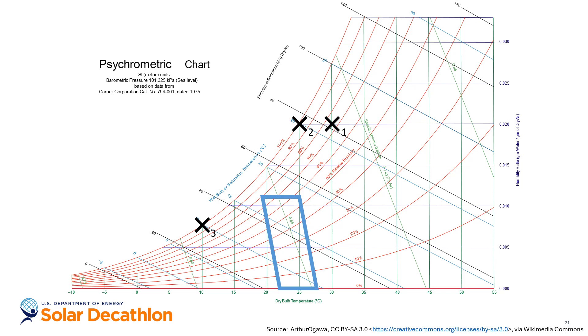We've now dehumidified the air by cooling it to the point where water is removed by condensing into liquid form. This is how most dehumidification processes work, but they result in air that is dehumidified but uncomfortably cold. So the fourth step is a reheat process to heat the air back to a comfortable temperature, moving horizontally to the right on the chart. To get from 30°C and 75% relative humidity to a more comfortable 23°C and 45% humidity, we had to cool, dehumidify, and then reheat the air. This demonstrates how HVAC processes occur to cool and dehumidify air.